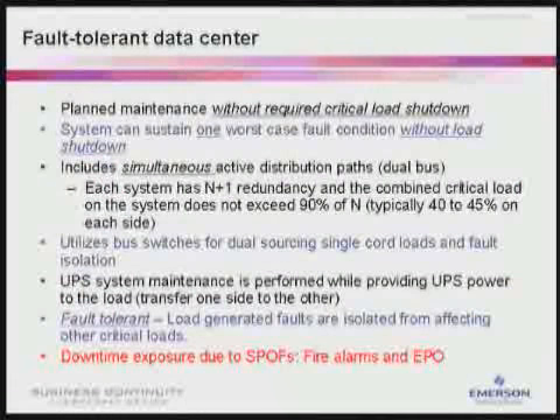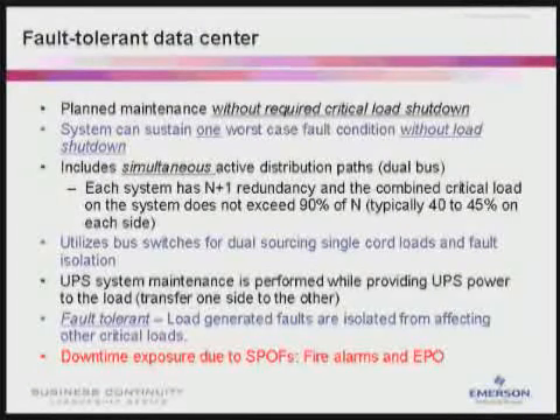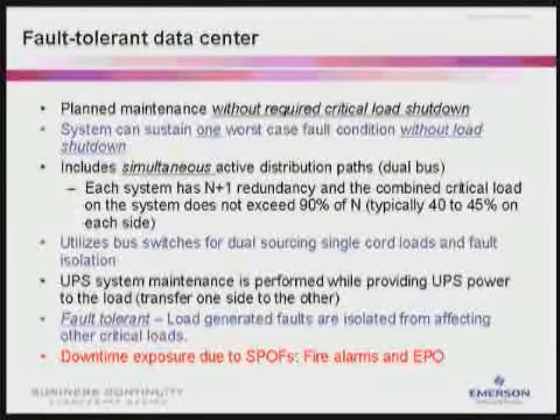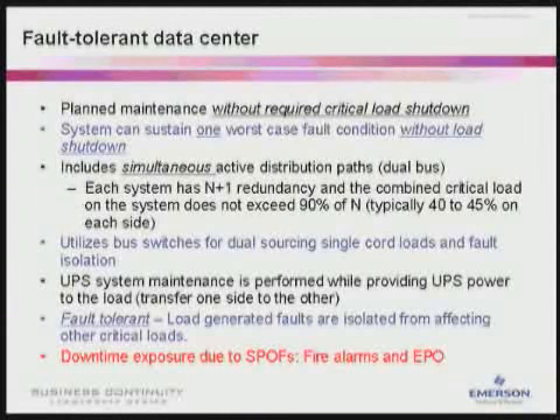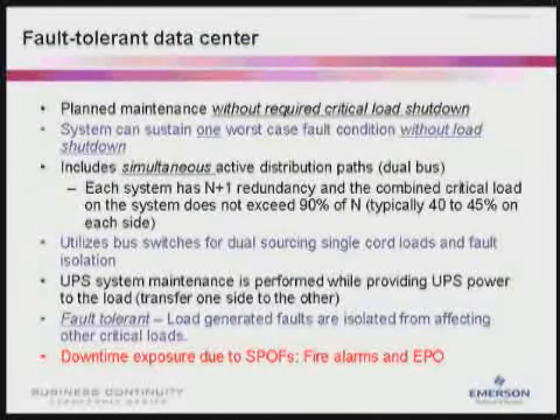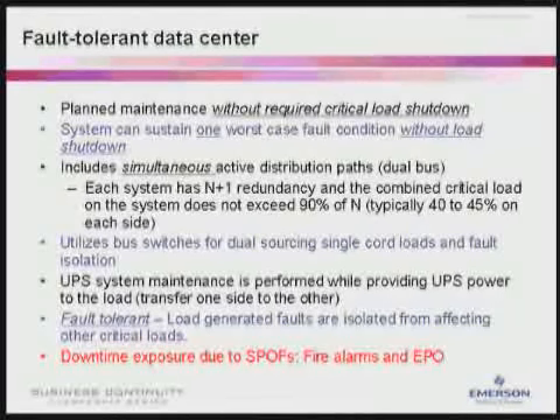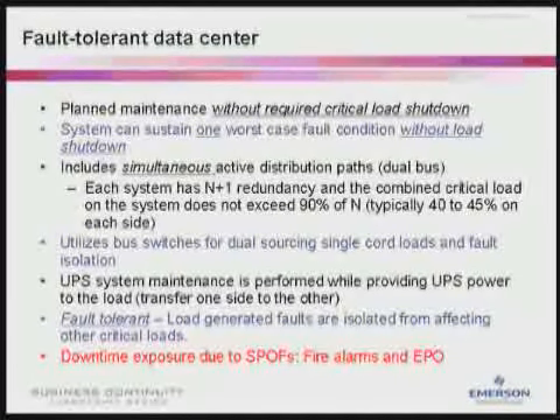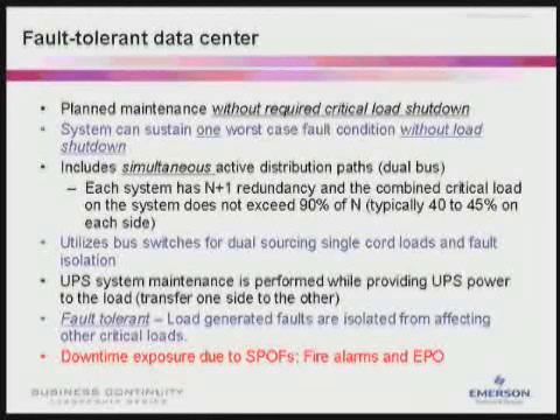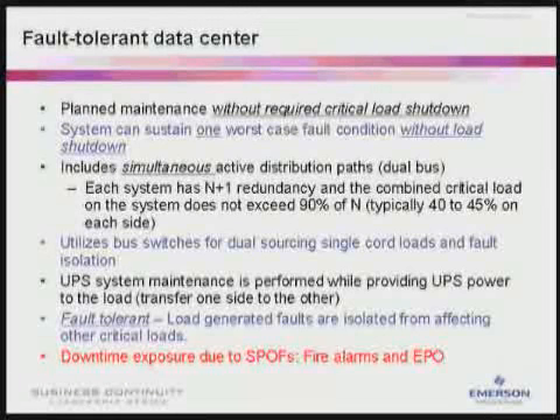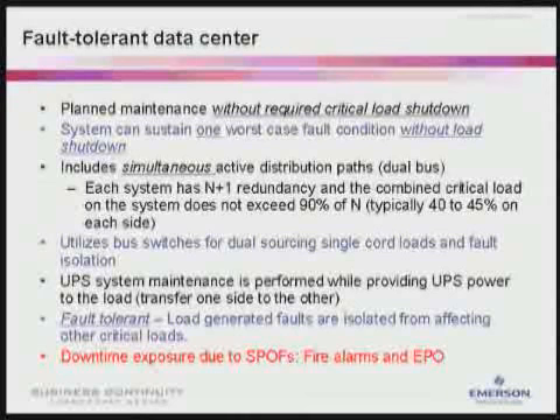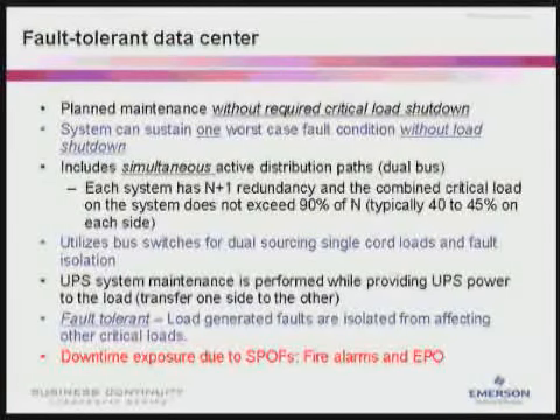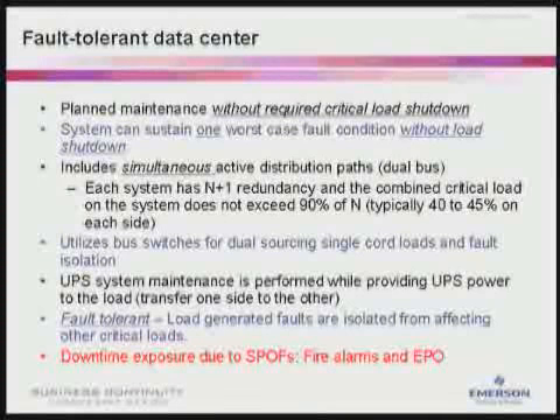In a fault-tolerant data center, the system can sustain one worst-case fault condition without load shutdown. It utilizes bus switches for dual sourcing, single-corded loads, and fault isolation. It is fault-tolerant in that load-generated faults are isolated from affecting the other critical loads. It includes simultaneous active distribution paths, dual bus. Each system has N+1 redundancy, and the combined critical load on the system does not exceed 90% of N, which is typically 40 to 45% on each side. There is still an exposure due to the single point of failure from fire systems and EPO.